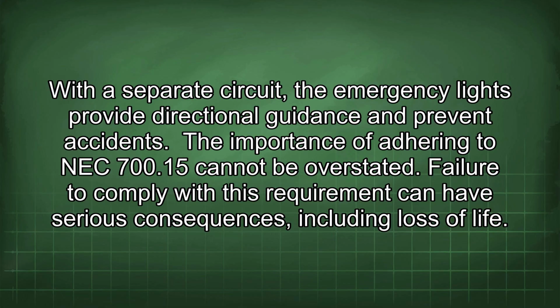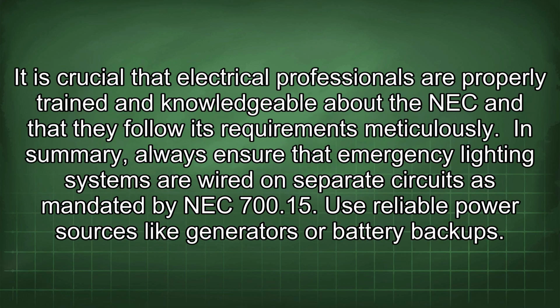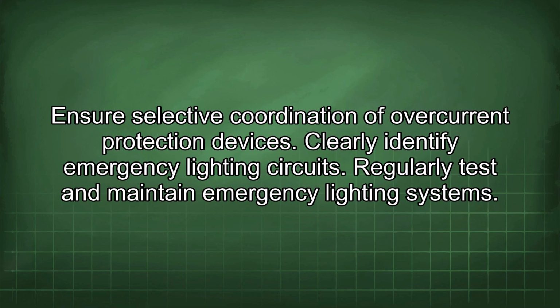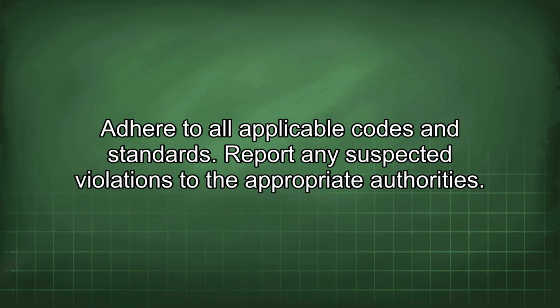The importance of adhering to NEC 700.15 cannot be overstated. Failure to comply with this requirement can have serious consequences, including loss of life. It is crucial that electrical professionals are properly trained and knowledgeable about the NEC and that they follow its requirements meticulously. In summary, always ensure that emergency lighting systems are wired on separate circuits as mandated by NEC 700.15. Use reliable power sources like generators or battery backups. Ensure selective coordination of overcurrent protection devices. Clearly identify emergency lighting circuits. Regularly test and maintain emergency lighting systems. Adhere to all applicable codes and standards. Report any suspected violations to the appropriate authorities.